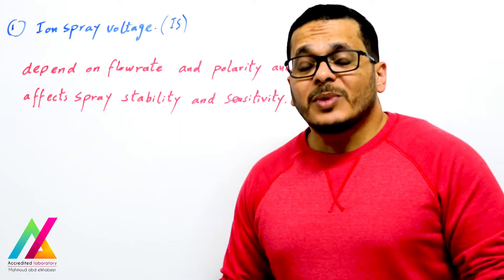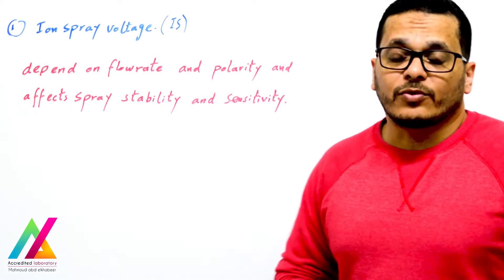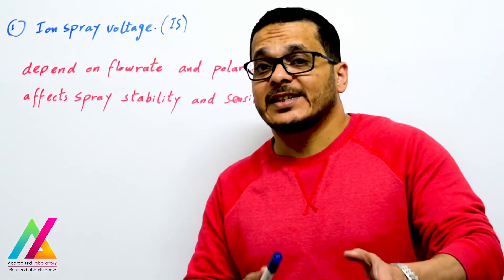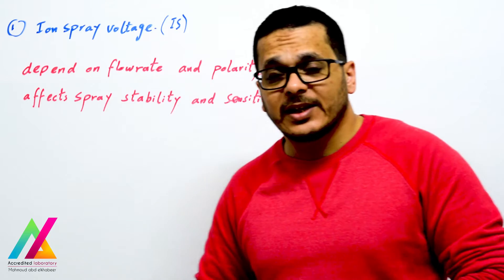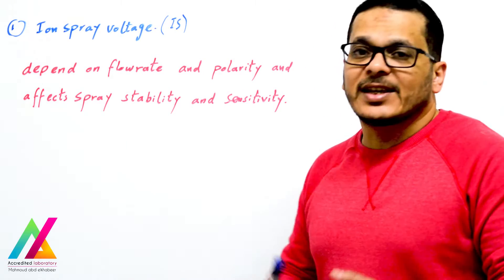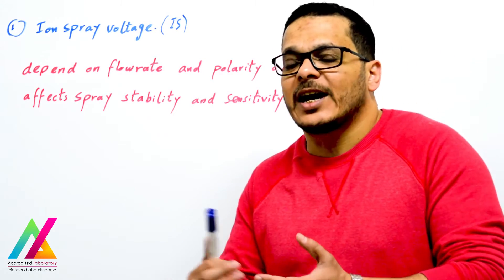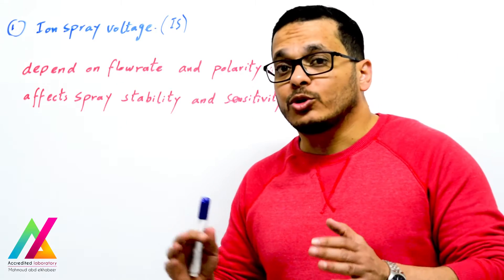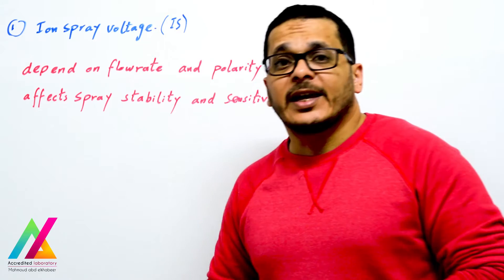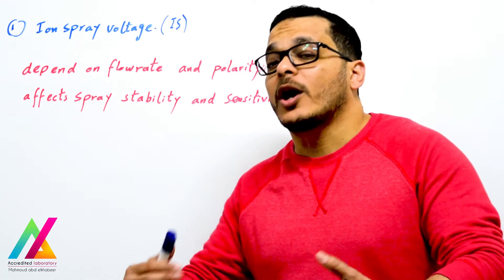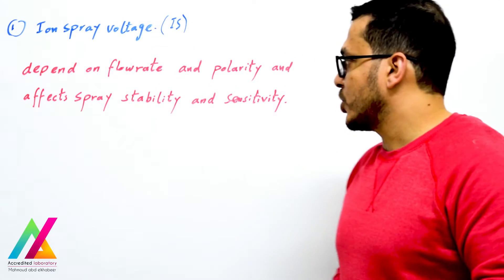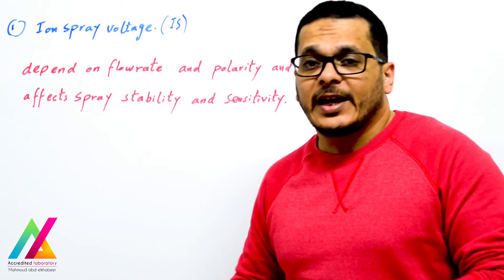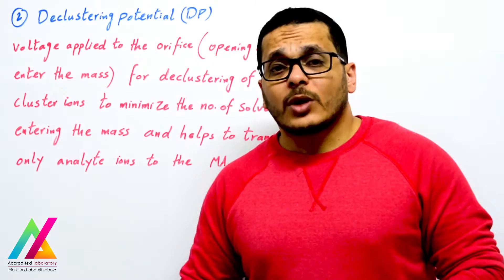This voltage depends on flow rate and polarity of compounds. If you increase the flow rate for your solvent carrying sample molecules coming from HPLC to the ion source, you need to increase the ion spray voltage to the optimum range to help the nebulizer gas and temperature ionize your sample molecules. It also affects spray stability and sensitivity.